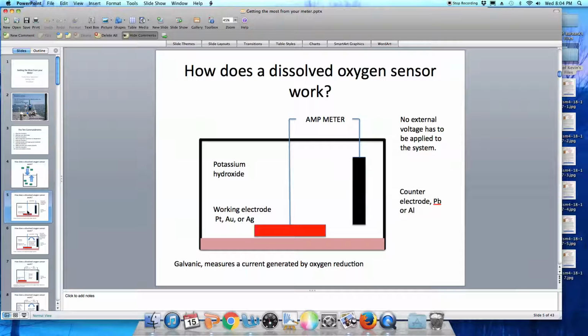So what are you going to see when you actually look at your dissolved oxygen sensor? The first thing you should notice is a permeable membrane at the bottom of the sensor and two metal electrodes inside a chamber that is filled with an electrolyte, potassium hydroxide in this example. There is a working electrode that is platinum, silver, or gold, and there is a counter electrode that is lead or aluminum.